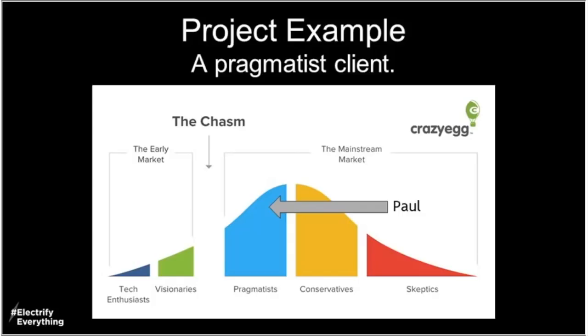And he's unique because he was actually a second-time client. So back when I was an installation contractor, he had one of the very few houses that we did top to bottom. So we did the basements, the walls, and the attic. We got a 50% reduction in the blower door out of that house, which for the program was so stunning that the test-out auditor, he didn't believe his gauge. So he actually took the blower door out, put it in a different door, and changed his manometer. And he came up with the same number, and we forever had his respect after that. And as it turns out, we had Paul's too.